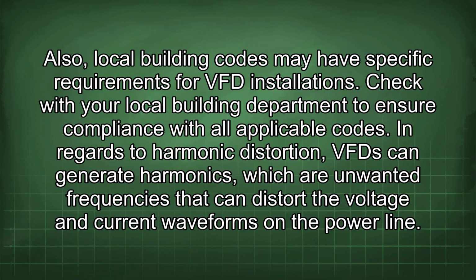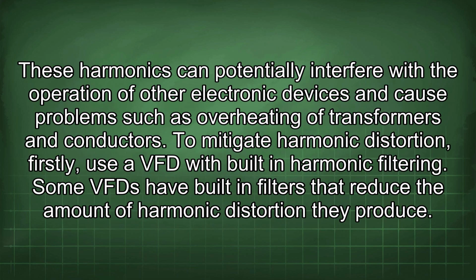In regards to harmonic distortion, VFD can generate harmonics, which are unwanted frequencies that can distort the voltage and current waveforms on the power line. These harmonics can potentially interfere with the operation of other electronic devices and cause problems such as overheating of transformers and conductors. To mitigate harmonic distortion, firstly, use a VFD with built-in harmonic filtering.